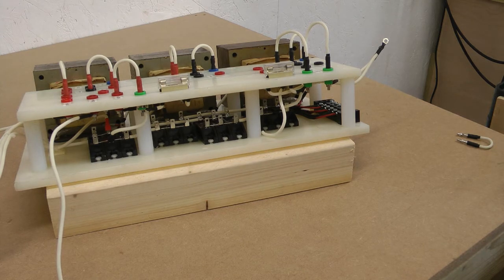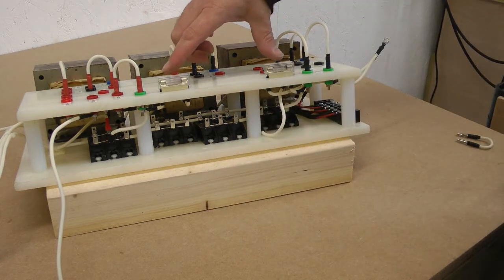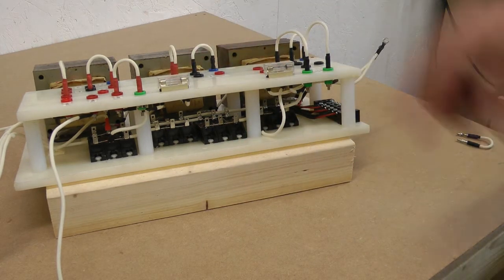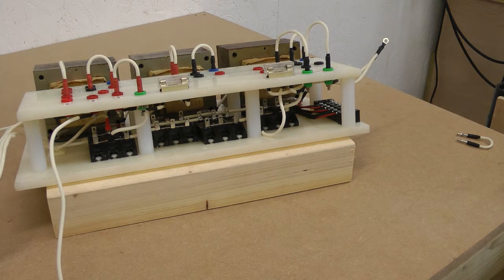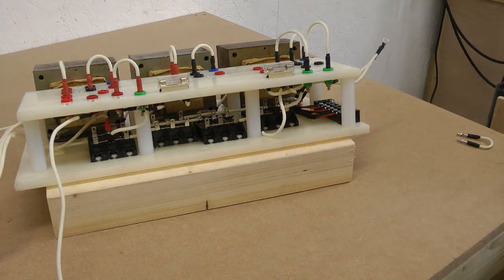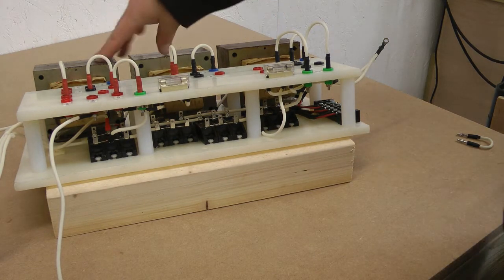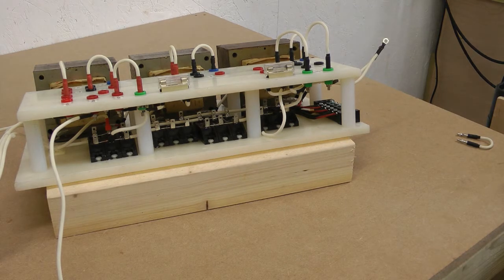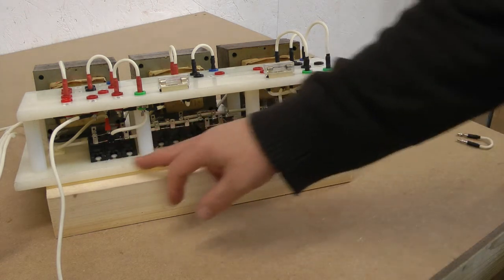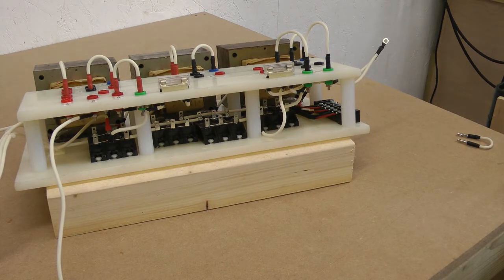Mostly you don't get burnouts or blowing semiconductors. This semiconductor bank is protected by the 2 fuses on the top here. That was primarily why I put them in. Originally I didn't have them, and I did end up with it going short circuit at the output when I was doing a certain type of test, which put too much current in the bridge. It pulled too much current. Obviously these transformers are able to push enormous amounts of current in a short circuit situation, with the shunts removed, and it basically just took out all 12 of the semiconductors.